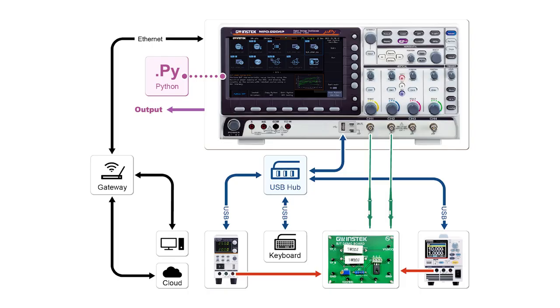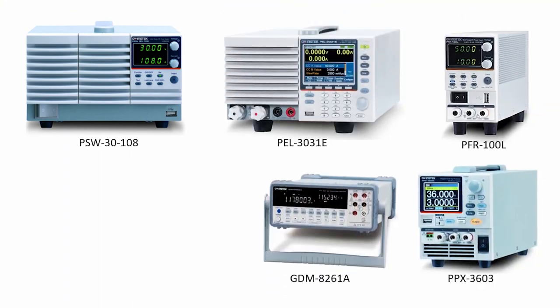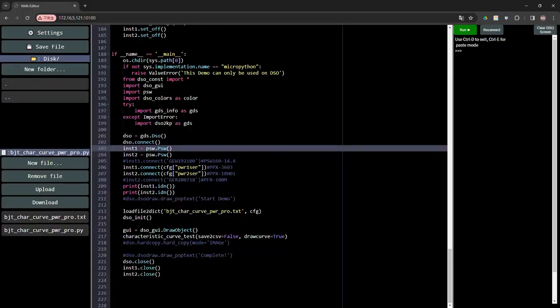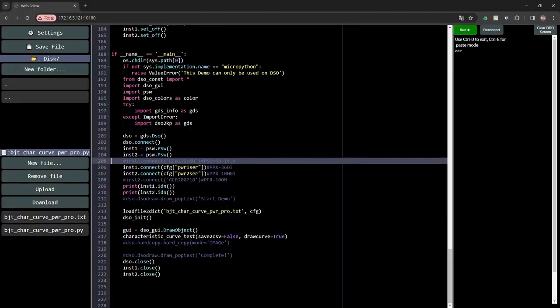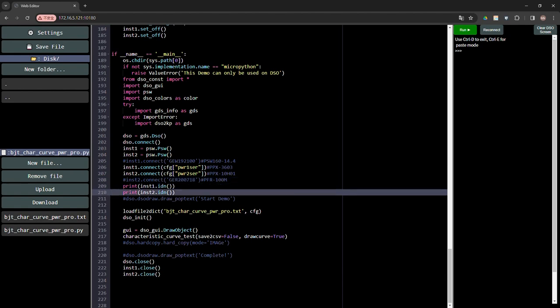Under Python script control, MPO-2000 can communicate with external USB devices through the USB interface using the CDC-ACM protocol for collaborative testing. Connectable devices include the PSW, PFR, PPX, PEL, and GDM series. MPO can also control external devices via LAN using the socket protocol, making it suitable for small-scale automation and semi-automation testing applications, saving engineers considerable time and effort.